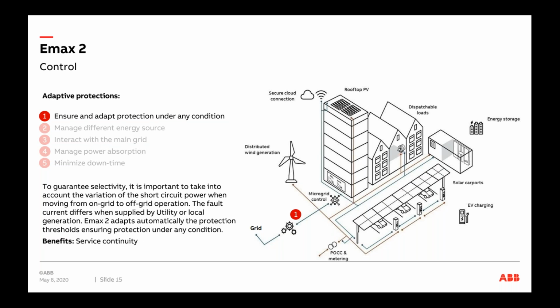So adaptive protections, that's one of the software functionalities we have with Emax 2. Now, this is available only from the Ekip Touch version. That's the trip unit type we trade in Australia and New Zealand. That's the main one, and we have a higher range, which we call the Hi-Touch. What adaptive protection allows us to do is guarantee selectivity. Now, when switching between two setups where you have a main grid and a microgrid, the protection levels or the power levels can be different. So you'd probably require two different sets of protection on each kind of source of supply.